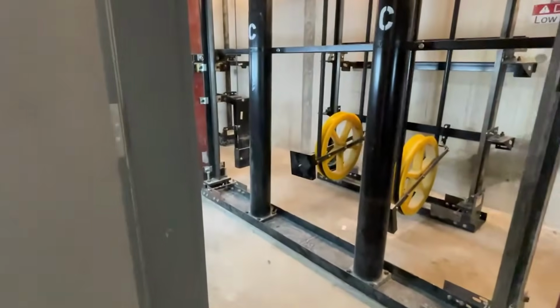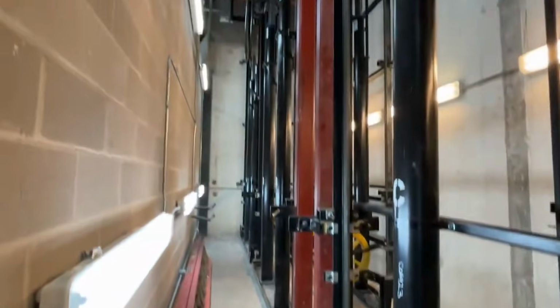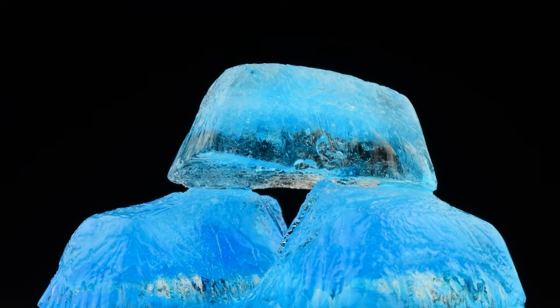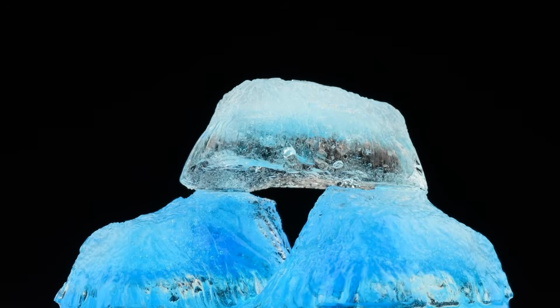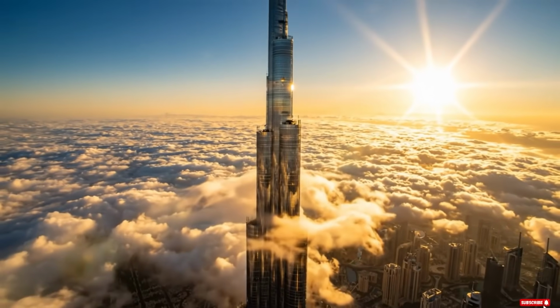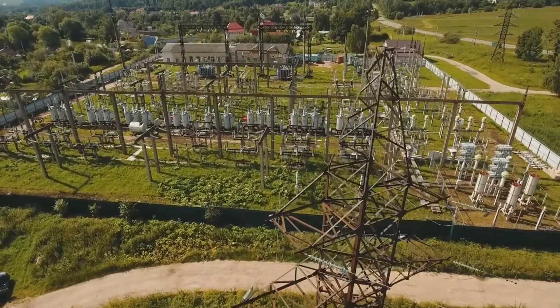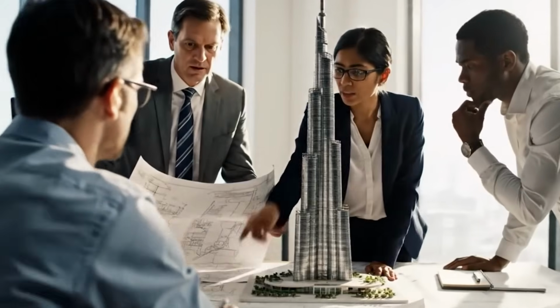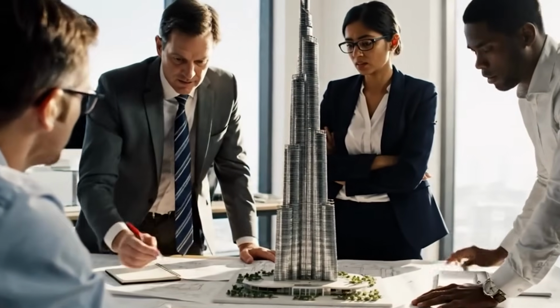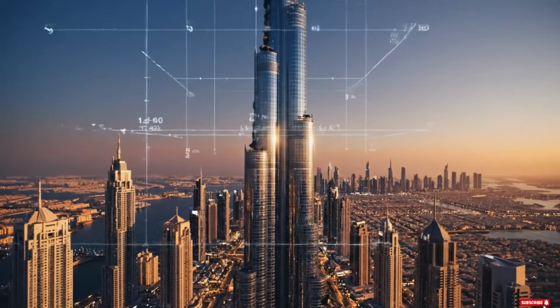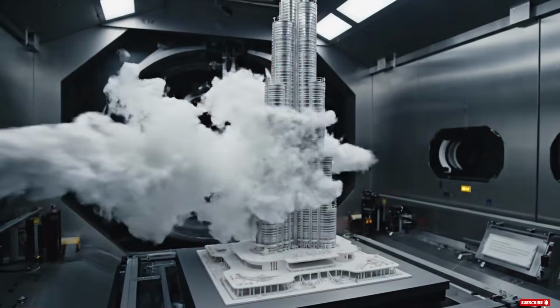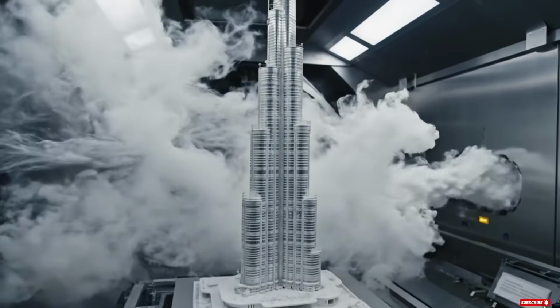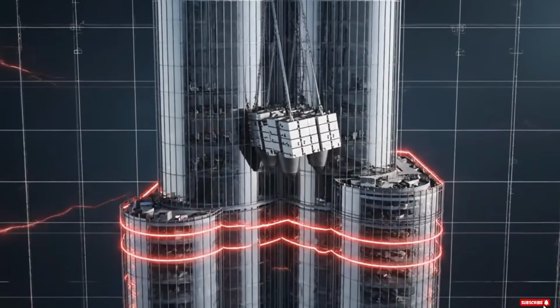But the real challenge was still ahead. At peak load, the Burj Khalifa requires approximately 10,000 tons of cooling capacity. To make that tangible, that is the equivalent of melting 10,000 tons of ice every single day. Conventional air conditioning at that scale would demand so much electricity during peak hours that it would threaten the stability of Dubai's entire power grid. So the engineers built something that sounds almost absurd until you understand the elegance of it. Every night, when electricity demand across the city drops and power is cheaper, the building's cooling plant manufactures millions of kilograms of ice slurry. Vast underground tanks fill with stored thermal energy.